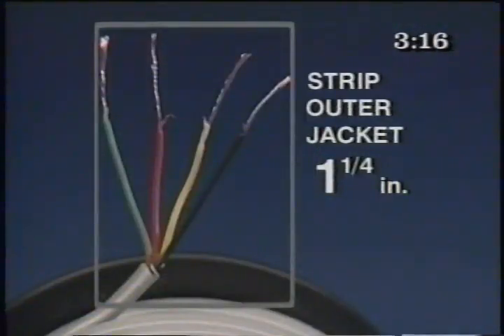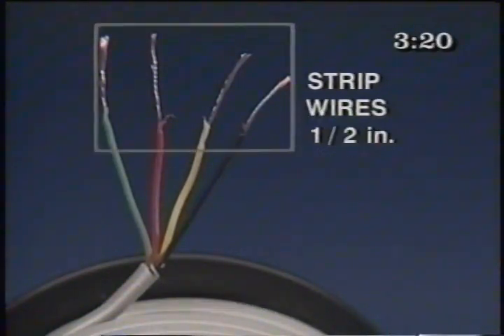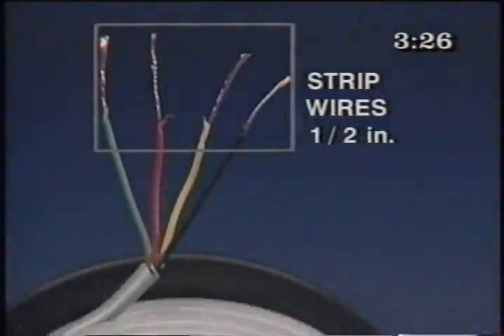Most connections require that you strip the cable wire's outer jacket back about 1 1/4 inches, and the individual wires should have about 1/2 inch conductor exposed. This leaves enough exposed wire to complete the connection without leaving excess wire to cause short circuits.